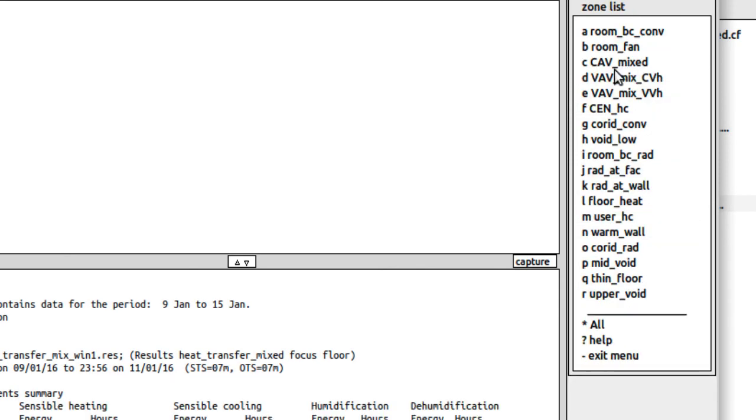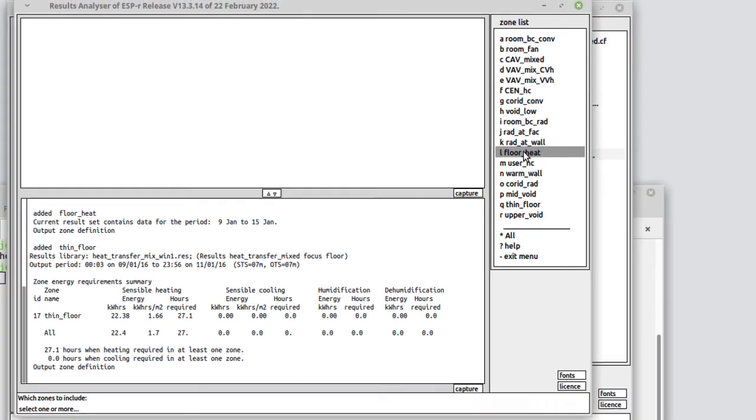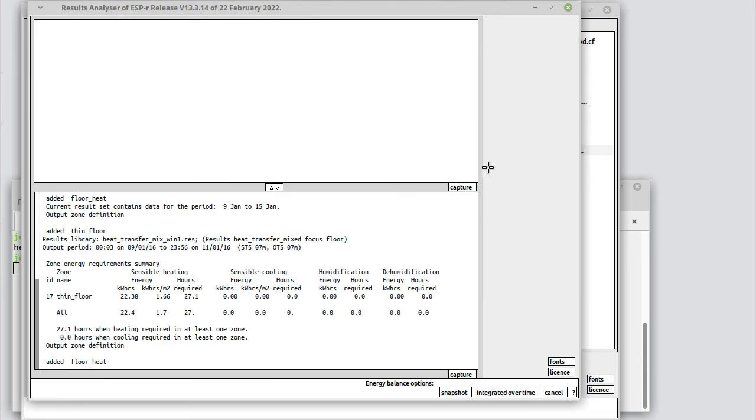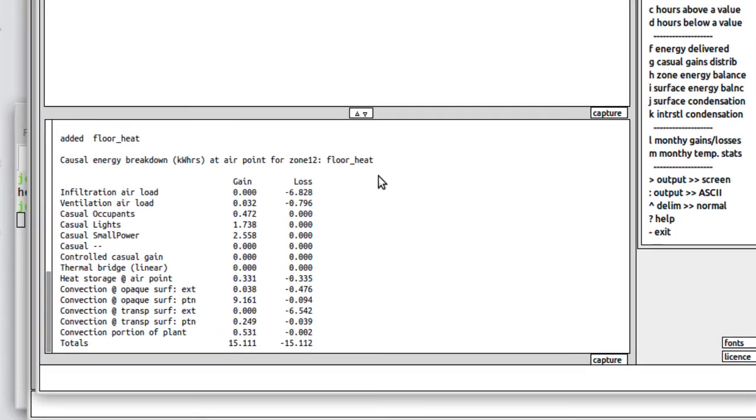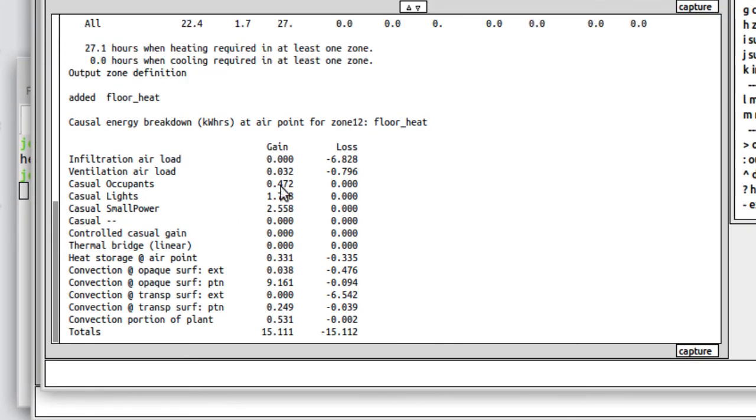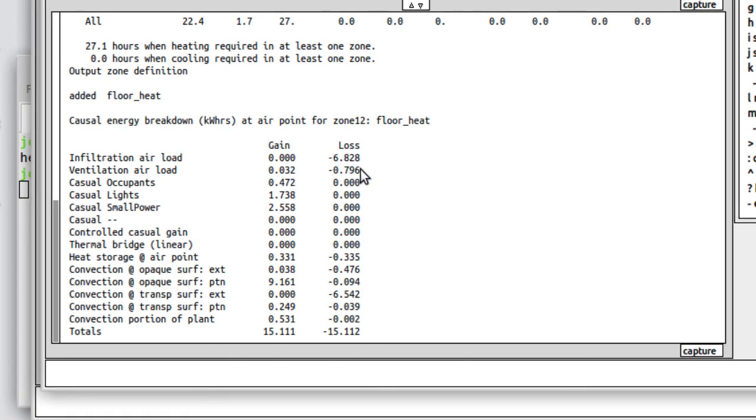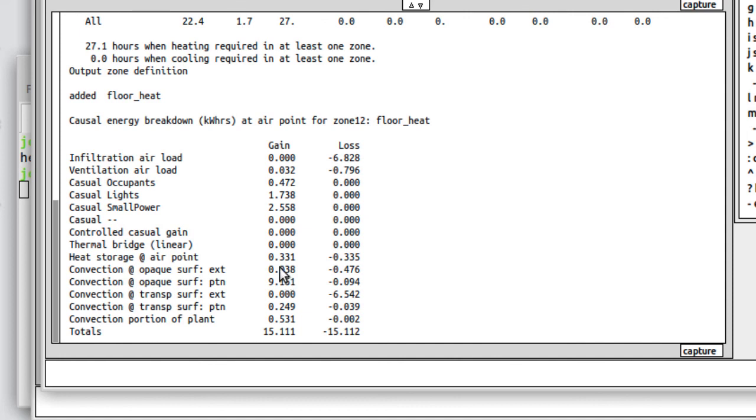We look at the zone energy balance. Let's select the floor heat zone. Integrated over time, gains and losses. So over those days, essentially our major losses are for infiltration. There's a little bit of air movement with other zones. We've got some occupants, lights and small power. We've got convection from opaque surfaces. That's our heat gain from the floor, effectively. We've got a little bit of opaque surface loss to the outside, and transparent loss to the outside is approximately the same scale as infiltration. And there's our energy balance.